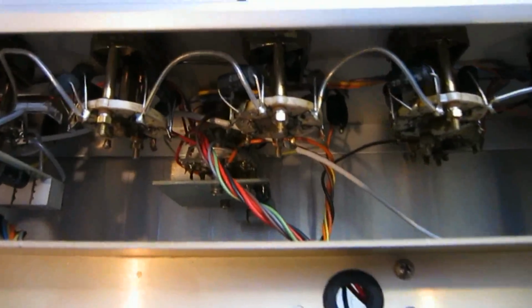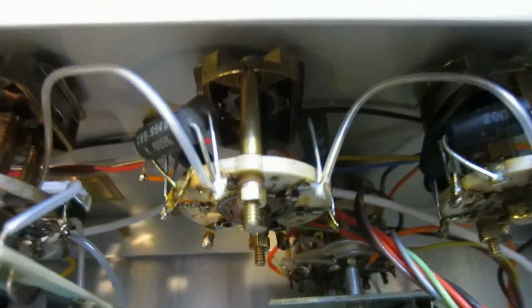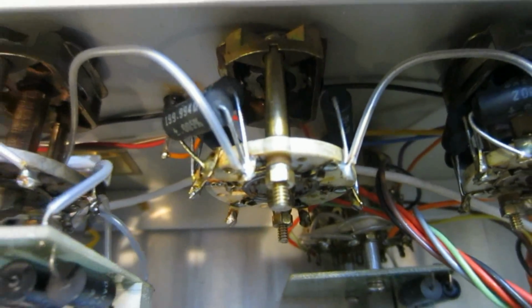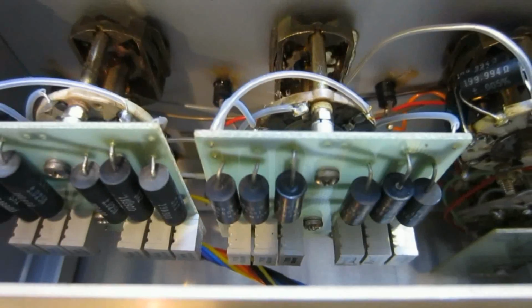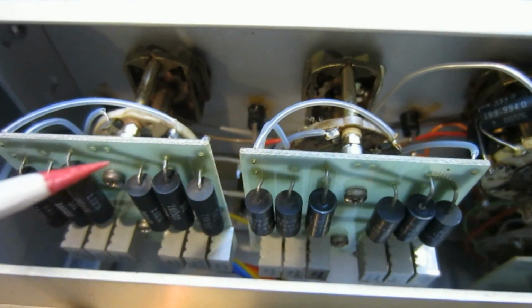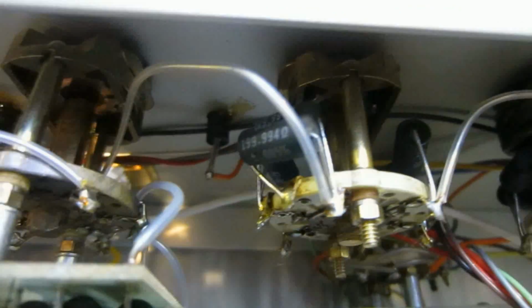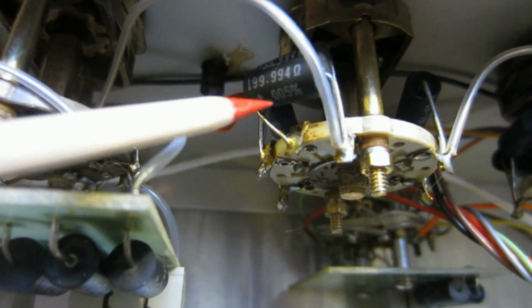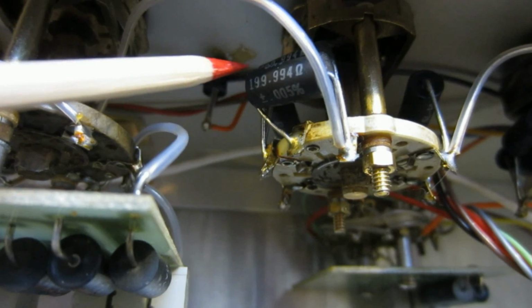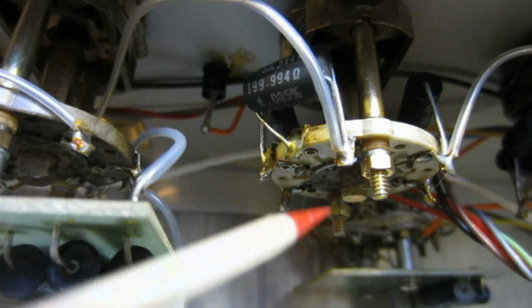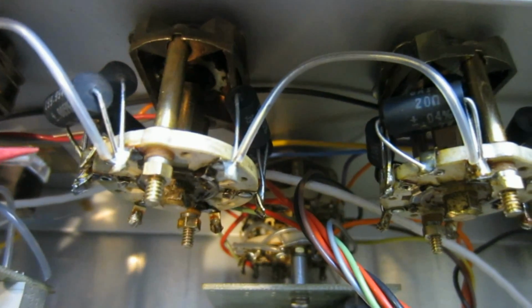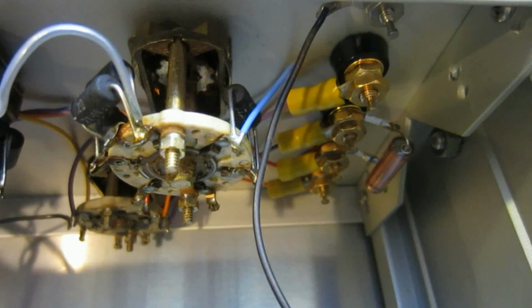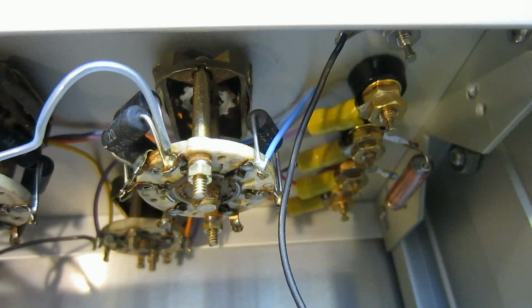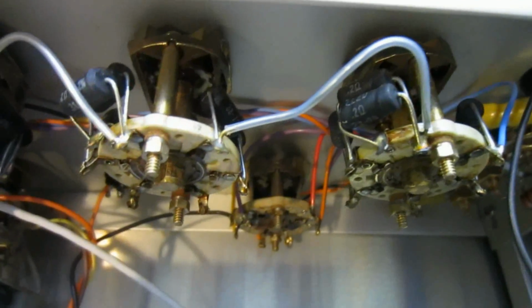Here we can take another look at these switches. Actually, I was wrong before - not all resistors are mounted on the boards. As you can see, these boards are for calibration, and these resistors are mounted on a separate board. But actually those voltage divider resistors, those high precision 199.994 ohm, 0.005% resistors, are soldered directly onto the switch. So on a unit like this, the only part that might fail is those switch connections, and it's definitely a good idea to make sure those are clean and well maintained.